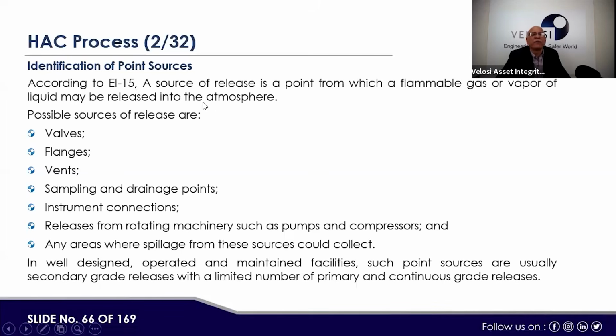EI-15 or IP-15, a source of release is a point from which a flammable gas or vapor of the liquid may be released into the atmosphere. Possible sources of release are valves and flanges. In valves, the stem can leak or the glands may leak, then flanges may leak, vents are there, and sample and drainage points are there. Instrument connections are also flange connections, like release from rotating machinery such as a pump, mechanical seals or the impeller area, or compressors. Then any area where spillage from these sources could collect.